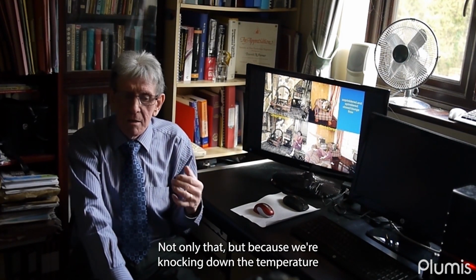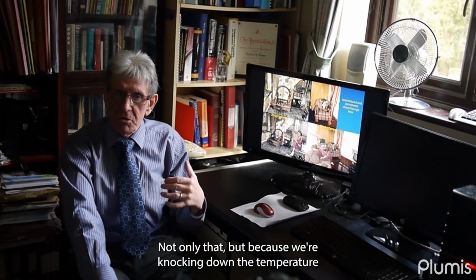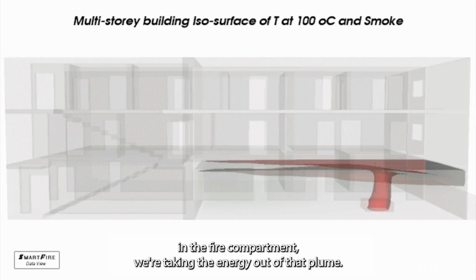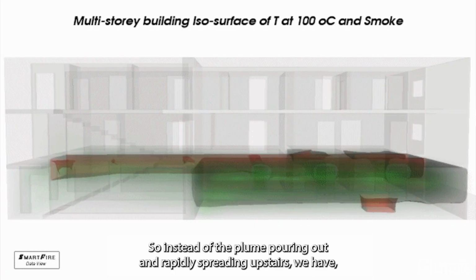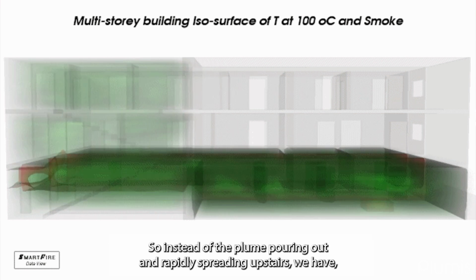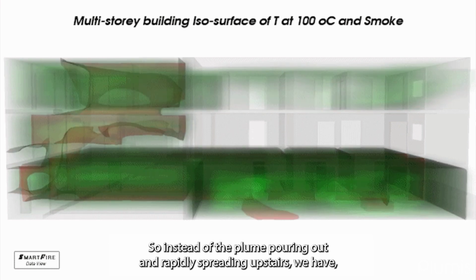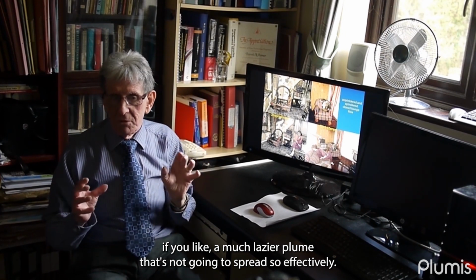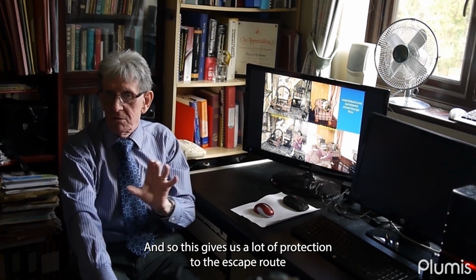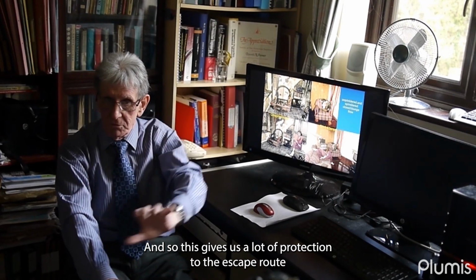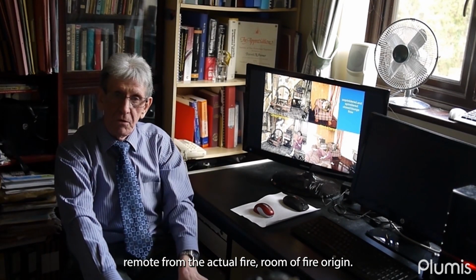Not only that, but because we're knocking down the temperature in the fire compartment, we're taking the energy out of that plume. So instead of the plume pouring out and rapidly spreading upstairs, we have a much lazier plume that's not going to spread so effectively. This gives a lot of protection to the escape route remote from the actual fire room of origin.